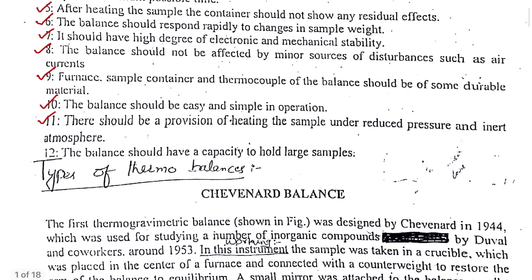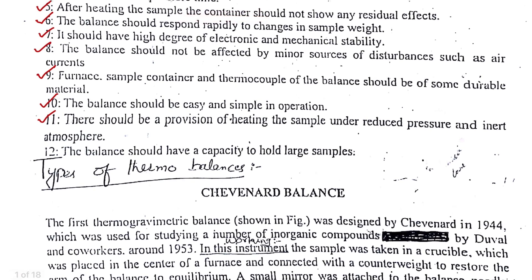The instrument should be such that the sample container should not show any residual effects. Residual effects means that when you take a second reading, the effects of the first reading should not disturb the second reading — in other words, the two readings should be independent of each other. This is possible only when we have a very clean sample container with no residues from the previous reading.